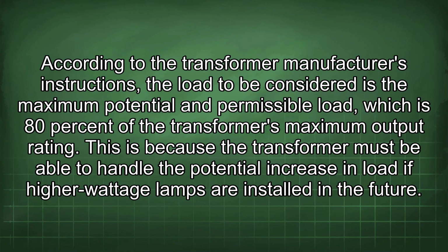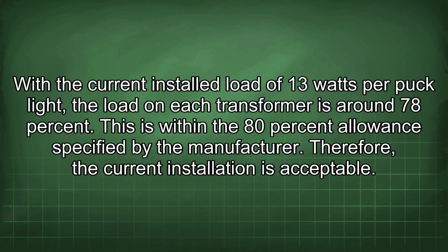According to the transformer manufacturer's instructions, the load to be considered is the maximum potential and permissible load, which is 80% of the transformer's maximum output rating. This is because the transformer must be able to handle the potential increase in load if higher wattage lamps are installed in the future. With the current installed load of 13 watts per puck light, the load on each transformer is around 78%. This is within the 80% allowance specified by the manufacturer. Therefore, the current installation is acceptable.